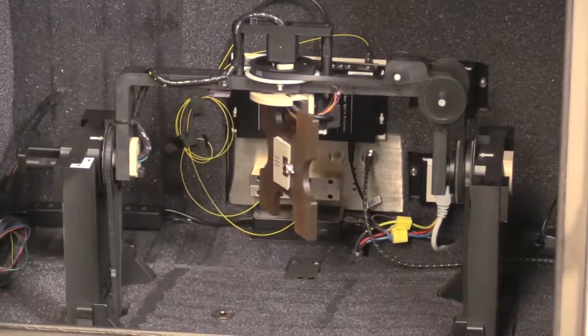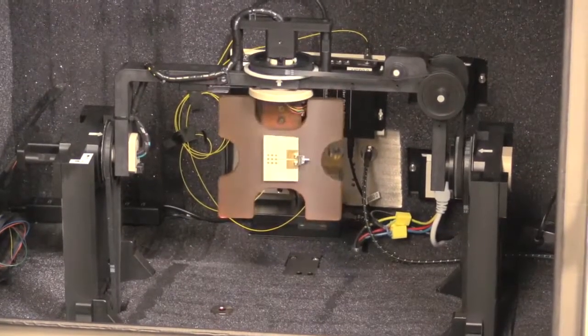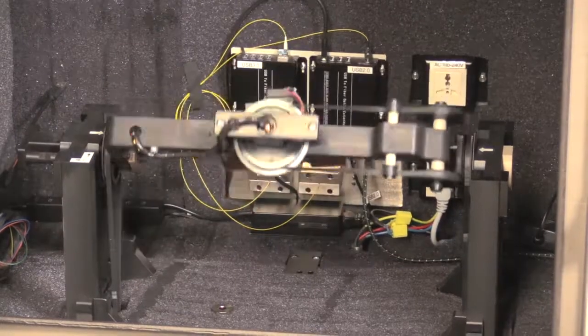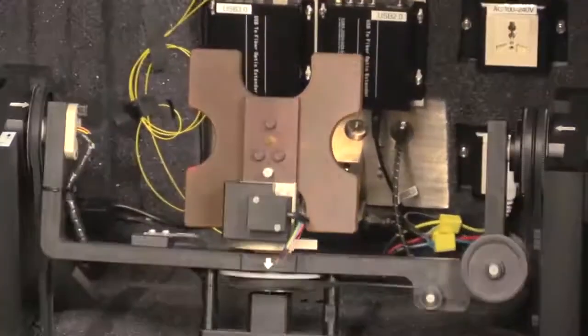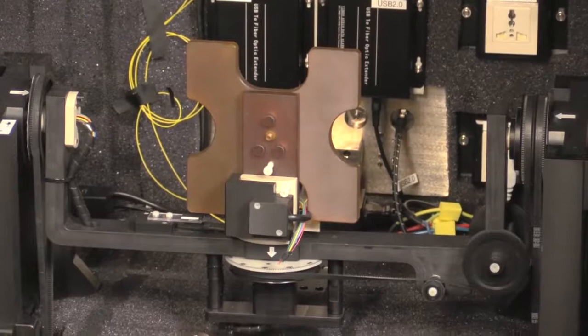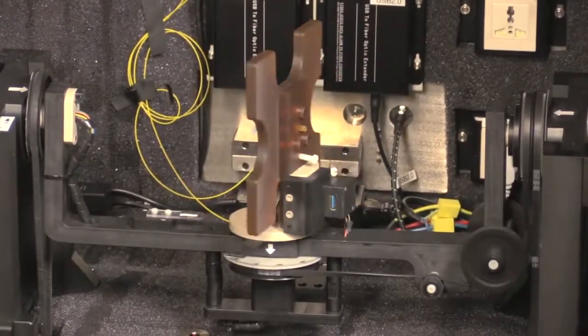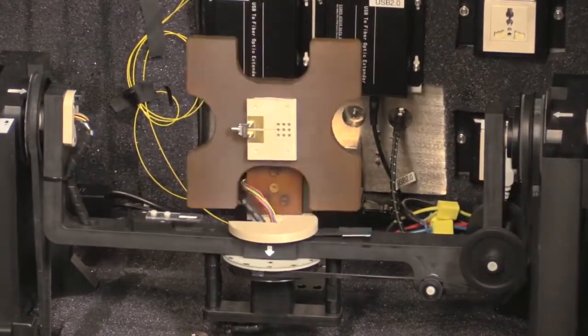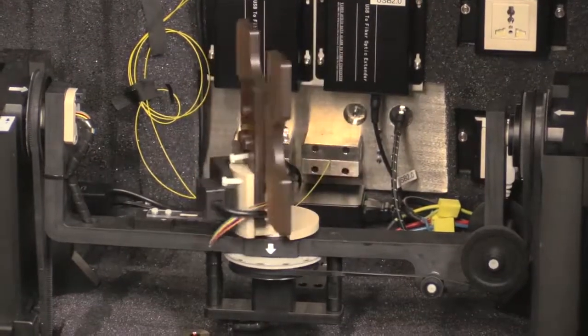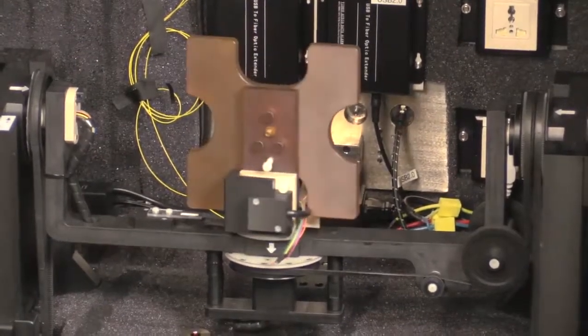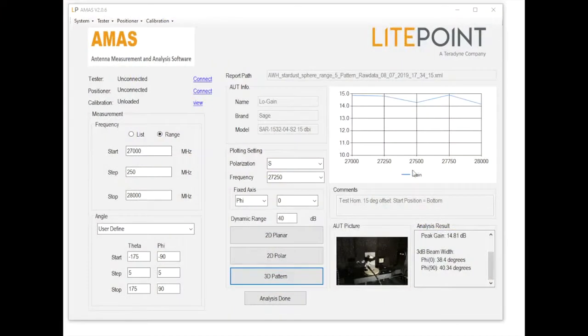Here we see the positioner adjust the device to a variety of angles. At each position, horizontal and vertical polarized RF measurements are being performed at the frequencies we specified in AMAS. During the measurement, the results are plotted so you can see real-time measurement data. After the data is collected, we use these analysis functions to analyze and view the data.